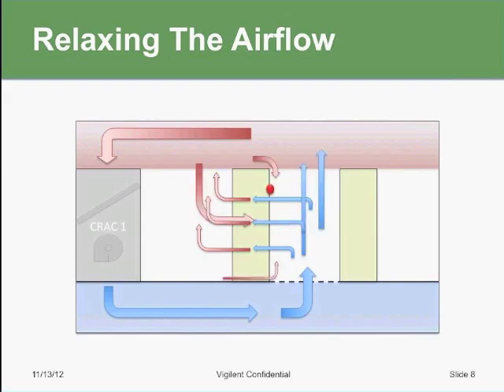But what actually happens when you have an excess amount of cooling capacity is you have an excessive amount of airflow. And so the airflow is actually bypassing the IT equipment and rising up to the ceiling and mixing with that hot thermal plenum. And what happens when cold air mixes with the hot thermal plenum is that hot air in the ceiling is actually displaced down into the environment where the IT equipment is. And it's displaced over the top of the racks, around the side of the racks, and even through the racks or under the racks, which results in mixing. And that's what causes hotspots. It's an excessive amount of airflow that results in mixing, which causes hotspots.